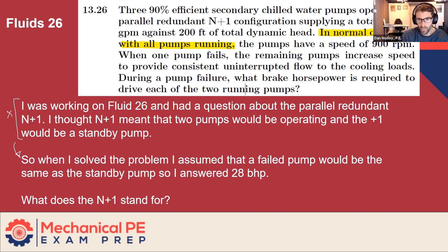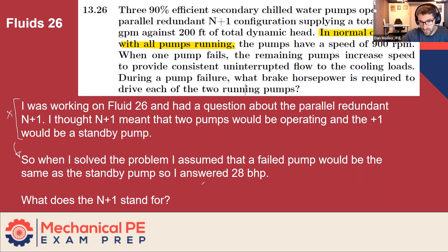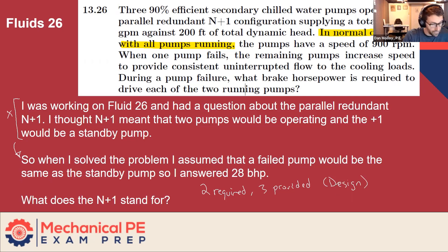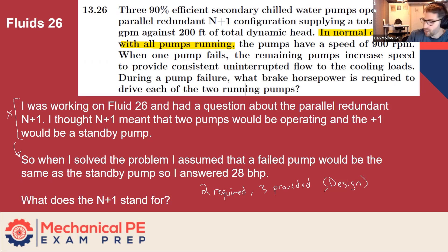So then the question becomes: what does N plus one really mean? Strictly speaking, N plus one describes the design intent. N plus one says you need two pumps required — we're going to provide three. That's from a design perspective, but that's kind of where it ends. When we look at it from an operational perspective, what are you actually going to do with those three pumps? Different operations will have a different preference as to how they want to do this and why.